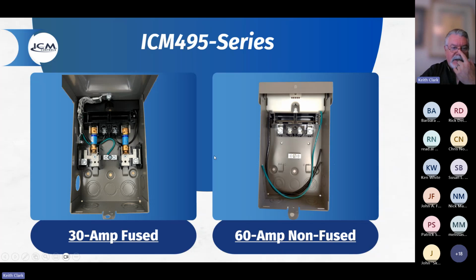We also have surge protection devices in disconnects now. We've got a 30 amp fused and a 60 amp non-fused, and this is a good way to go as well. It offers the same protection as 517A and is pre-wired, so it makes life pretty easy. 517, should you have to change it, is very easy to change, which is a nice feature as well, and it can be used for multiple devices or on a single breaker and that type of thing.